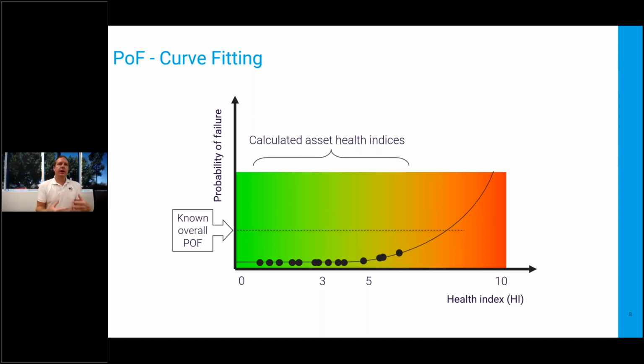But in CNAIM, they have commonly agreed K values for each of the asset classes that are modeled. Whereas in CBRM, we define a number of failure modes, and then we do this exercise of curve fitting. So the K value that we use in CBRM is tailored to the known or expected failure rate for that failure mode for your assets in your operating environment and your network.